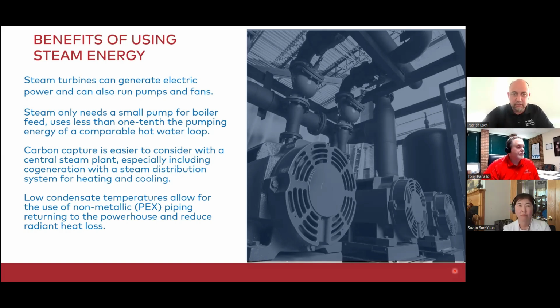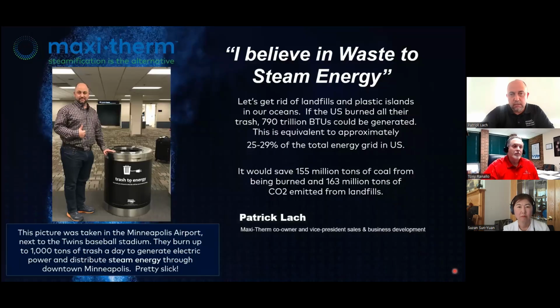Carbon capture is easier to consider with a central steam plant, especially including cogeneration with a steam distribution system for heating and cooling. And you know, when you have low condensate temperature, it allows you to use non-metallic PEX piping for a condensate pipe, because we can provide low temp condensate under 200 Fahrenheit at all times, depending on your hot water set point. Next one. I will leave you with this final slide.